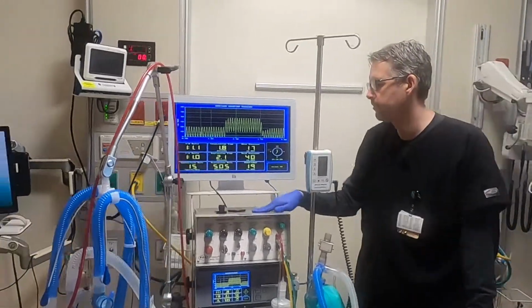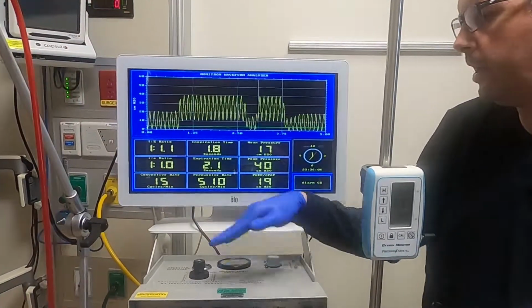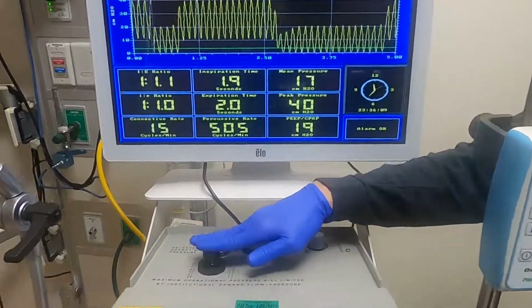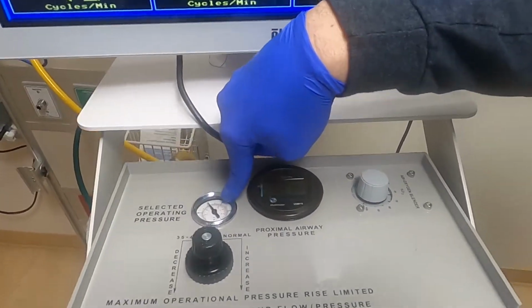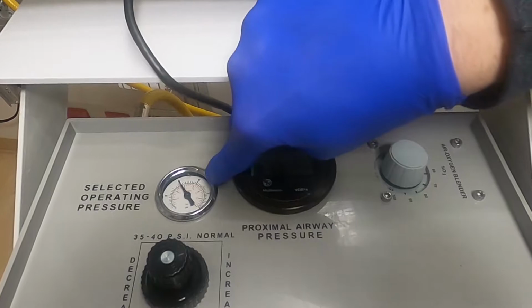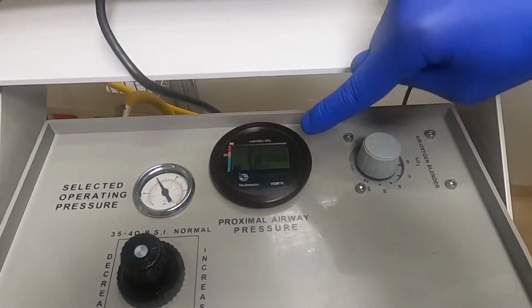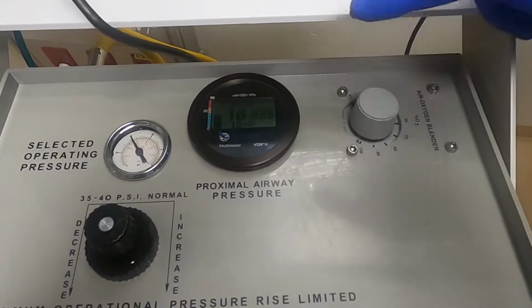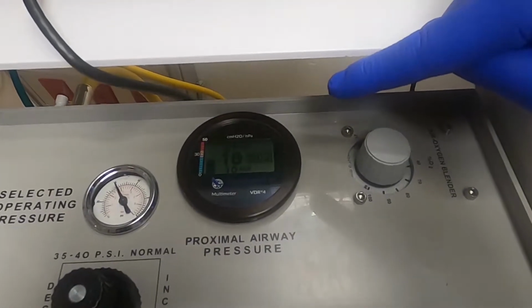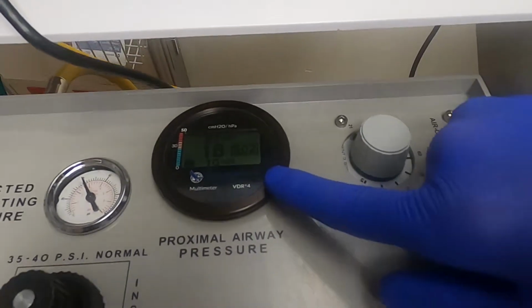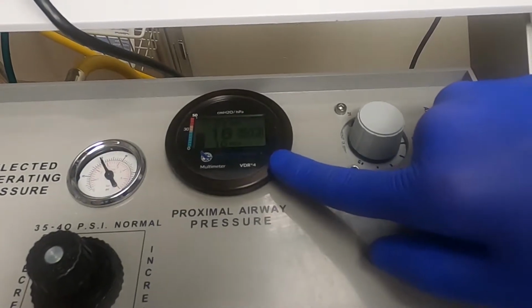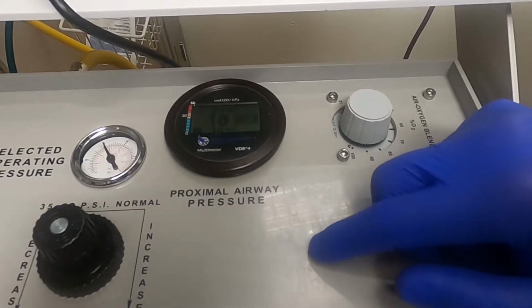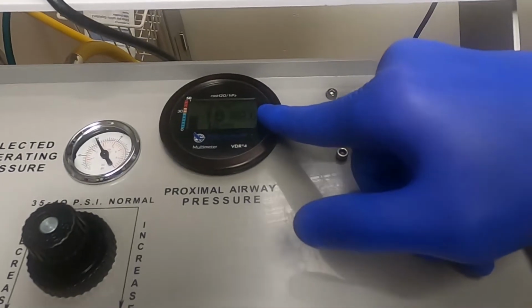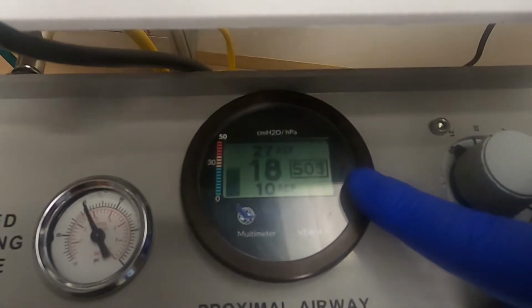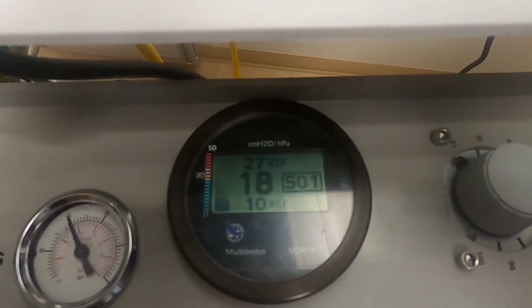Let's look at the top of the machine. Here we have where our working pressure is set. You see our gauge here is at about 40, so that's going to be dependent on the size of your patient. Here we have our pressure readout gauge. You can see the top number is 27, that's your average inspiratory pressure. Bottom number is 10, that's your average expiratory pressure. The middle number is your mean airway pressure. And then over on the right here is the rate, the high frequency rate.